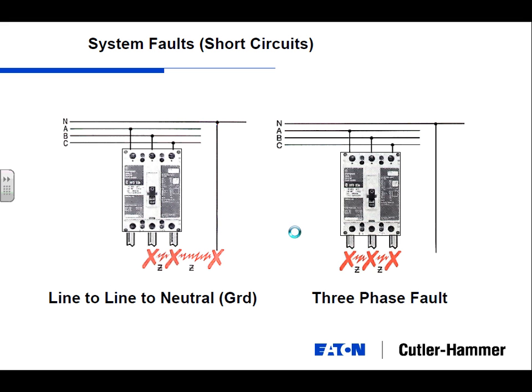When it happens, it's usually when you're starting the equipment up for the first time. You go in, contractor, you install equipment, you're putting everything together, and maybe somebody accidentally leaves his wrench sitting across the circuit breaker, and it's close enough to the phases where electricity can travel through air. Remember that. Air is resistance, but it can still travel through air. And that could be a situation when you first turn on the equipment that you basically get all three phases tied together in a worst-case scenario. Once you're up and running and your power system is being used, this is less likely, and you're more likely to get one of the other types of faults.